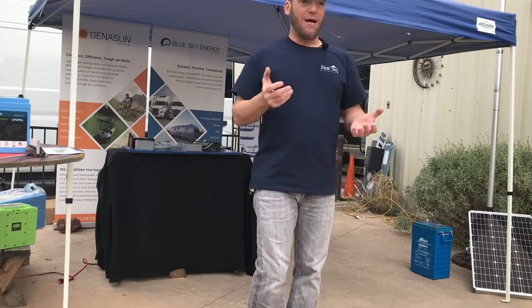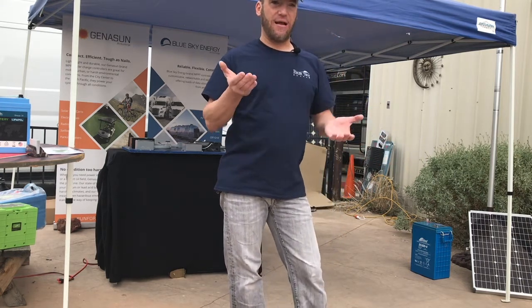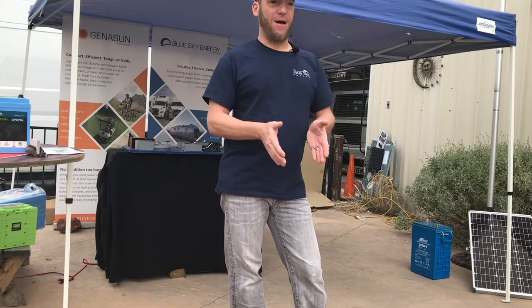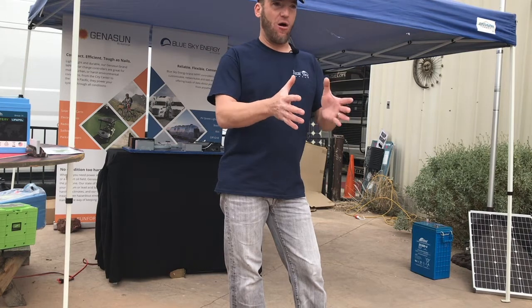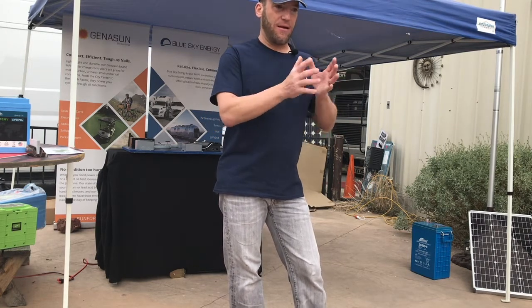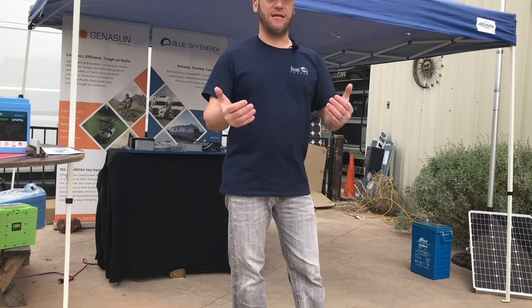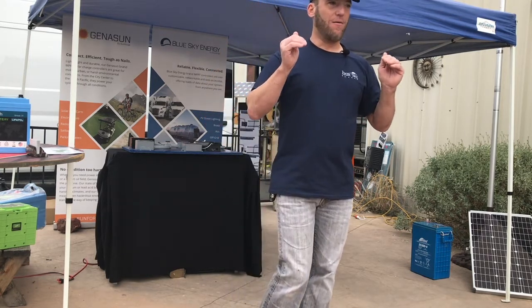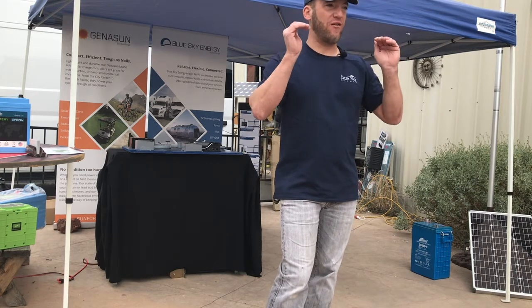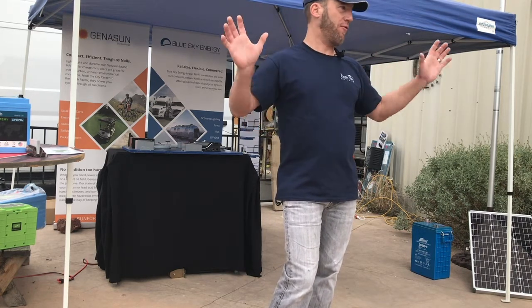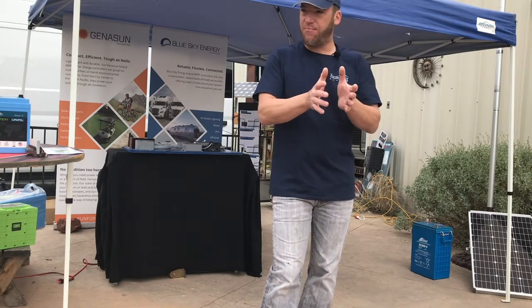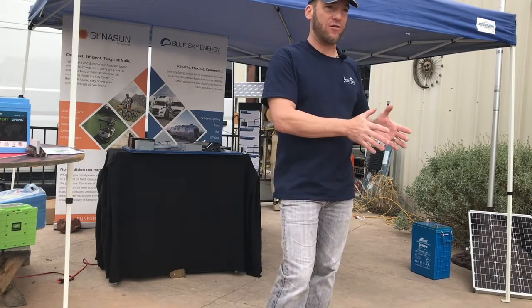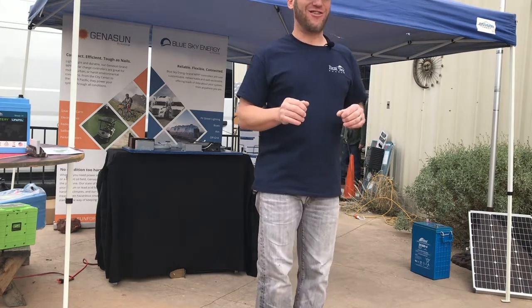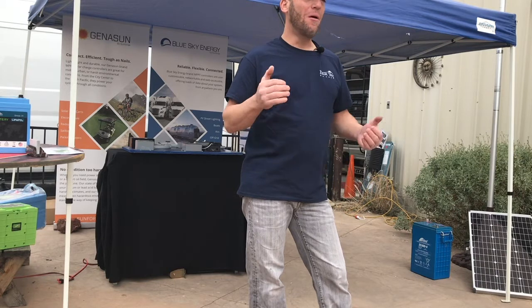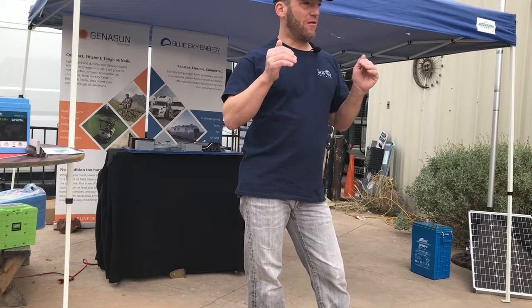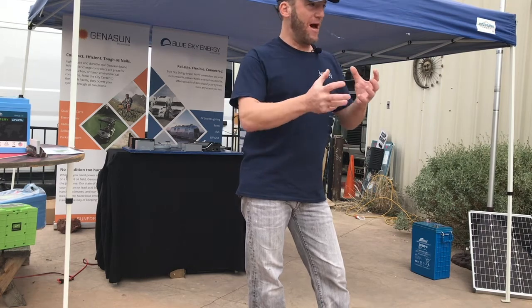Now, at the absorption voltage, it's kind of like picking the worst of two evils. In a lead acid battery, there's a secret sauce or paste on all the lead plates that keeps them healthy, but this secret sauce degrades whenever your batteries are at this higher voltage. So you don't want to hold that voltage unnecessarily long. That's why you don't keep a battery at 14.4 forever — you're degrading this special chemistry, which varies between manufacturers, kind of like the Kentucky Fried Chicken secret recipe. But you need to get to that higher voltage long enough to keep your batteries from sulfating.